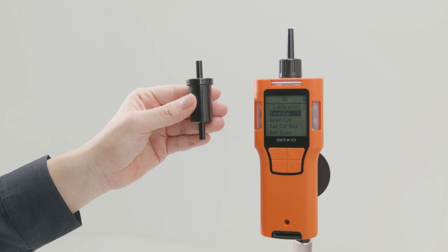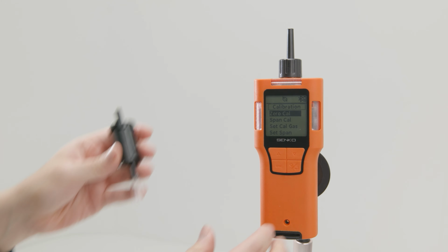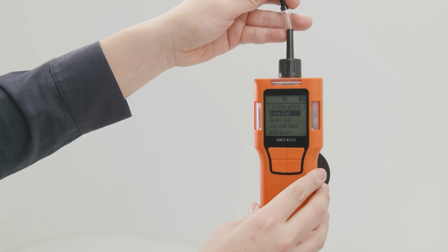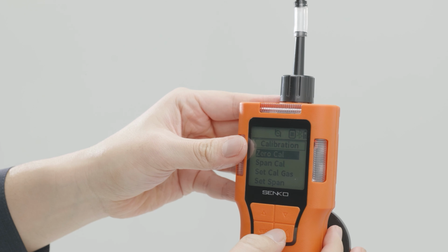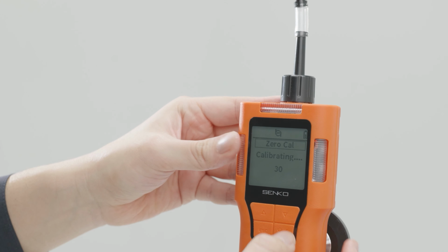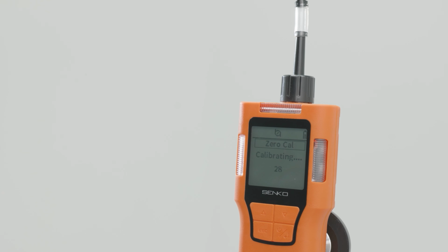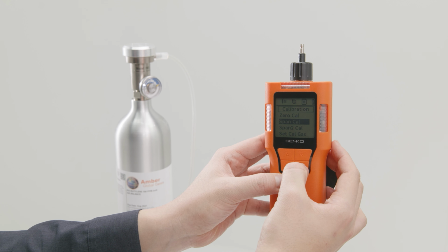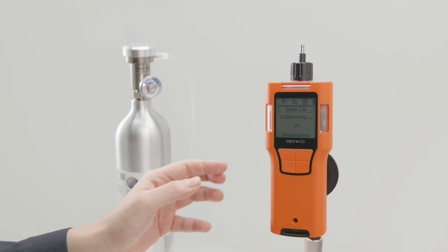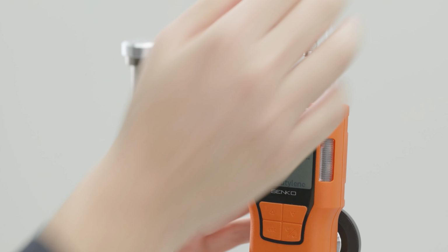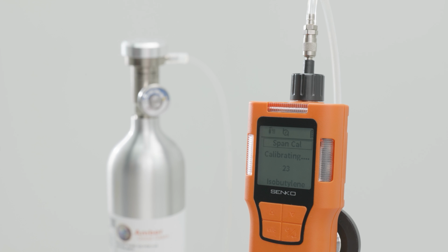Zero calibration is a method of setting a reference value in clean air, and span calibration performs calibration using standard calibration gas. Span calibration is a method of improving accuracy across a wide measurement range by using high concentration standard gas. In the calibration menu, the gas type and concentration to be used for calibration, namely the span value, can be set directly. The device automatically compensates the measured value based on the set calibration gas.